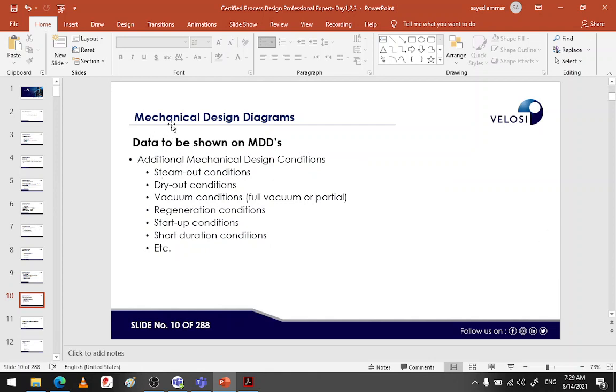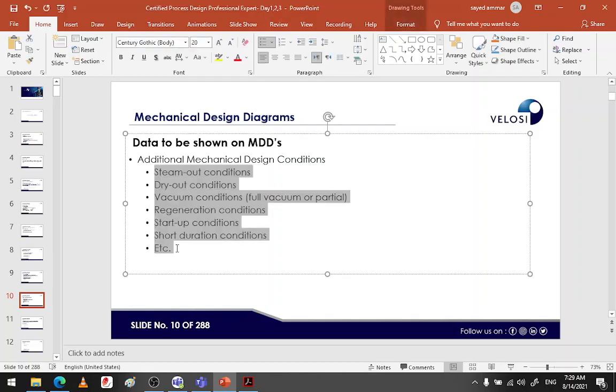Okay, why are we using mechanical diagrams? This will be in the commissioning phase. Why? We have additional uses for the mechanical design conditions in commissioning: steam-out condition, where we purge with steam, or drying condition, or vacuum condition, or regeneration condition, startup conditions, and short duration conditions. All of this can be extra additions for the mechanical design diagrams. Yes.